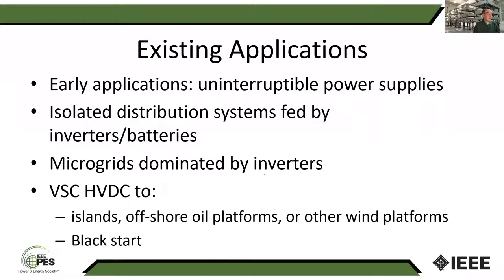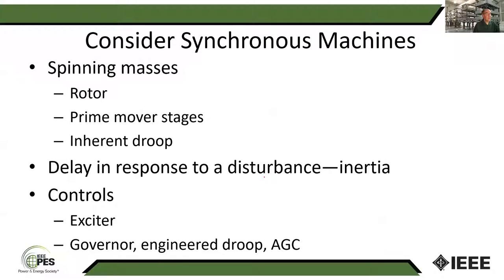Not that long ago, there was a demonstration in Europe showing the ability of using a voltage source converter HVDC scheme to do black start on an AC system. Some other things to think about with these grid forming inverters is, consider synchronous machines. We have this large spinning mass, right? And we have some inherent droop. So if the mechanical power in is less than the electric power out, it starts pulling kinetic energy out of the rotor and the machine starts to slow down.